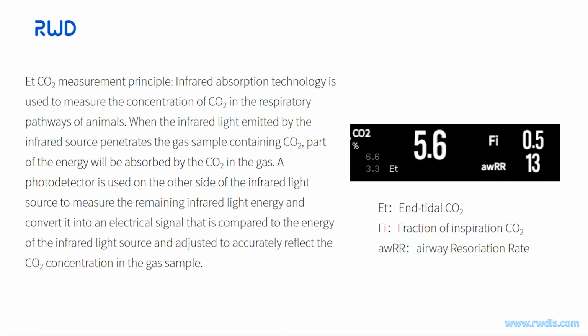End-tidal carbon dioxide measurement principle. Infrared absorption technology is used to measure the concentration of carbon dioxide in the respiratory pathways of animals. When the infrared light emitted by the infrared source penetrates the gas sample containing carbon dioxide, part of the energy will be absorbed by the carbon dioxide in the gas.